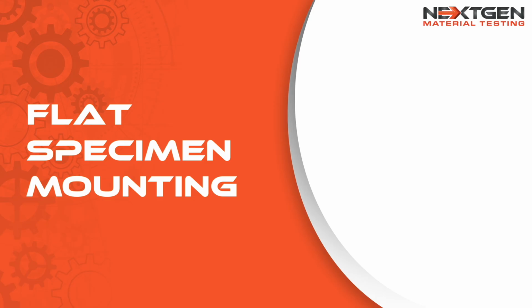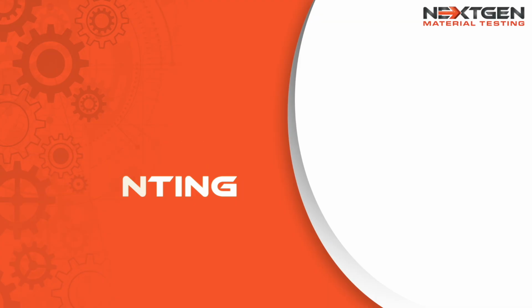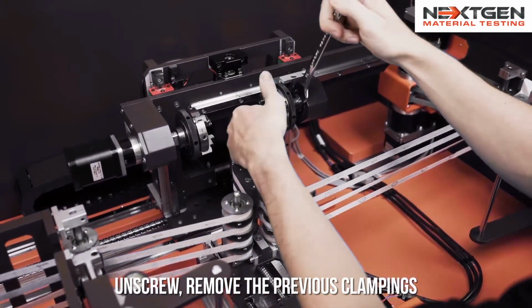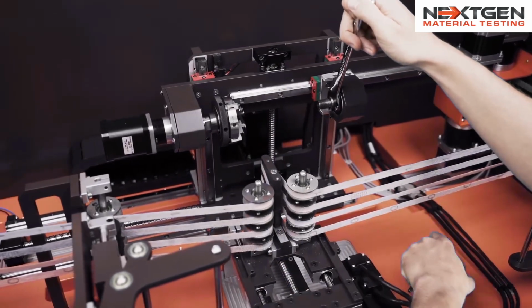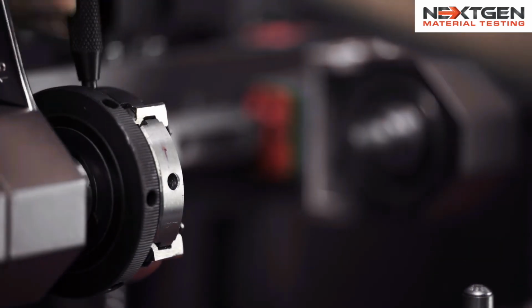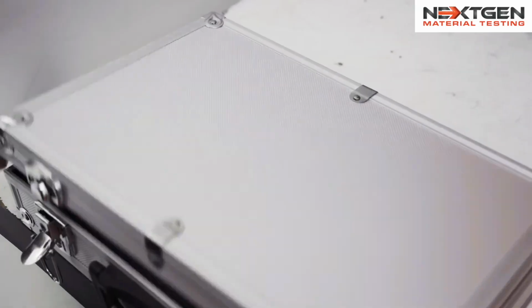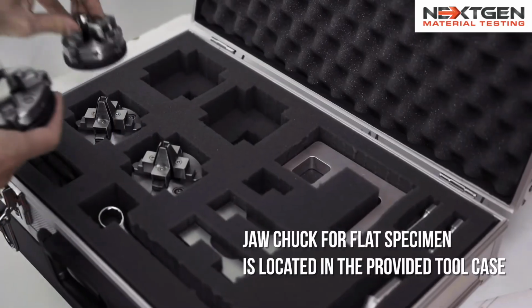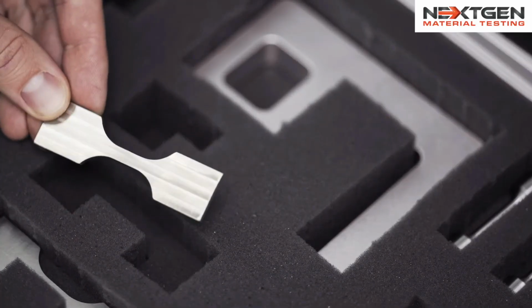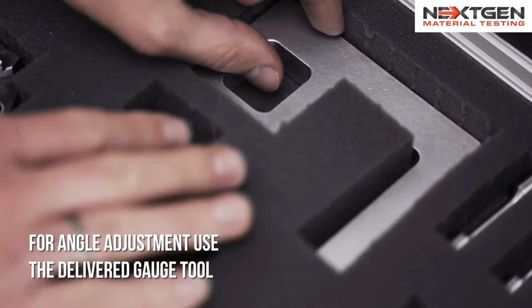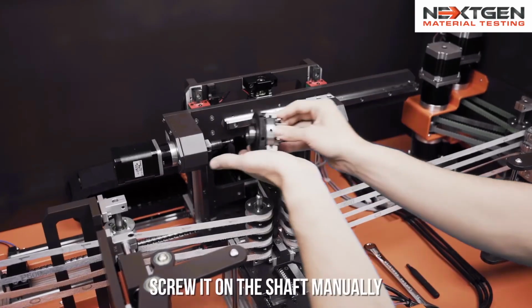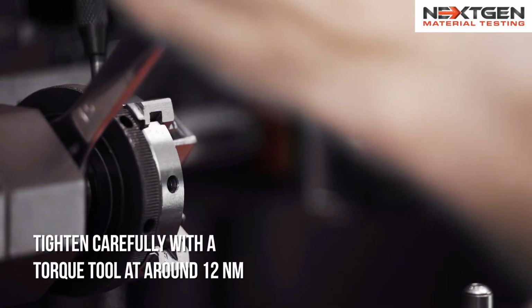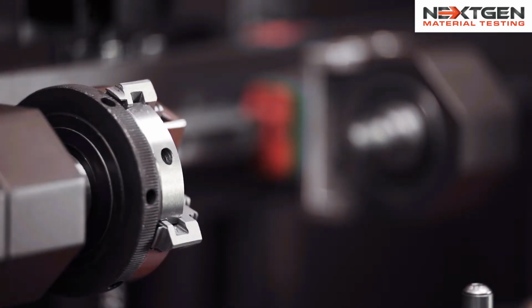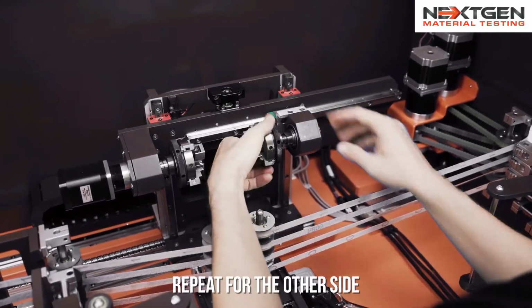Flat specimen mounting. Remove the previous jaw chuck. Locate the flat specimen jaw chuck in the tool case. Use the gauge tool for angular alignment. Thread it onto the shaft. Tighten to approximately 12 Newton meters. Repeat for the other side.